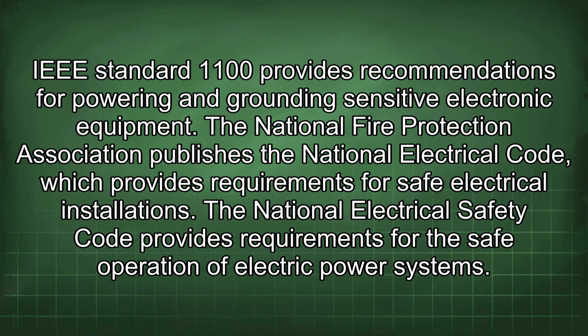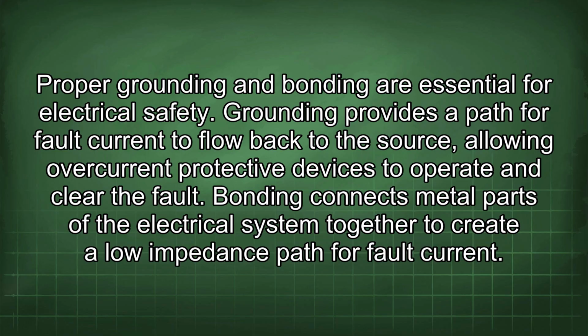The National Fire Protection Association publishes the National Electrical Code, which provides requirements for safe electrical installations. The National Electrical Safety Code provides requirements for the safe operation of electric power systems. Proper grounding and bonding are essential for electrical safety. Grounding provides a path for fault current to flow back to the source, allowing overcurrent protective devices to operate and clear the fault. Bonding connects metal parts of the electrical system together to create a low-impedance path for fault current.